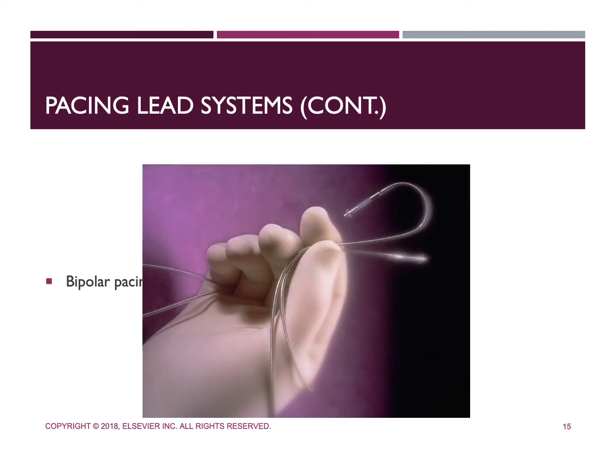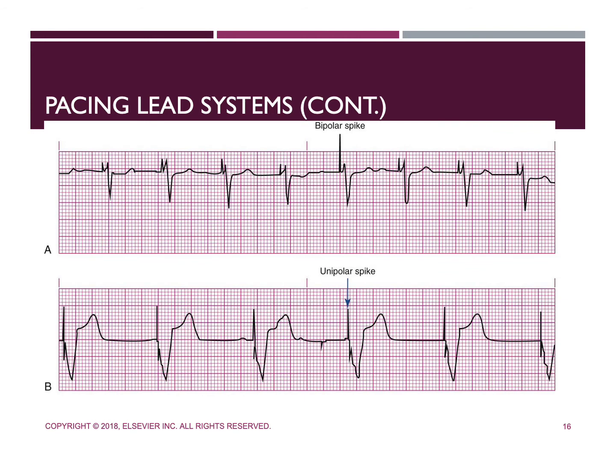Example of a bipolar pacing lead. A bipolar lead system contains a positive and negative electrode at the distal tip of the pacing lead wire, which temporary transvenous pacemakers use as a bipolar lead system. A permanent pacemaker may either have a bipolar or unipolar lead system. Bipolar and unipolar pacing. The first box, A, shows a pacemaker spike produced by a bipolar lead system. In the second box, B, a pacemaker spike produced by a unipolar lead system. The pacemaker spike produced by a bipolar lead system is smaller than that of a unipolar system because of the shorter distance between the positive and negative electrodes.